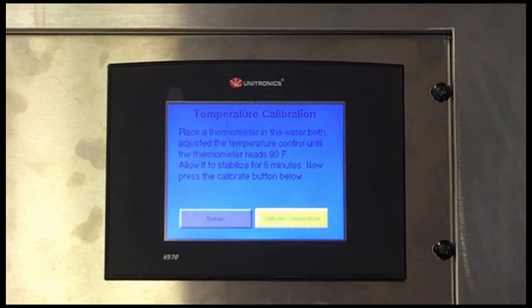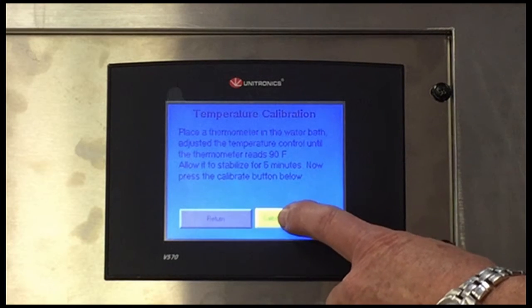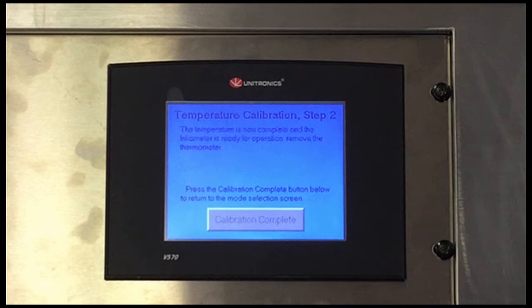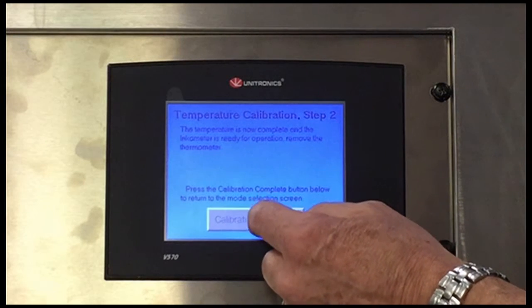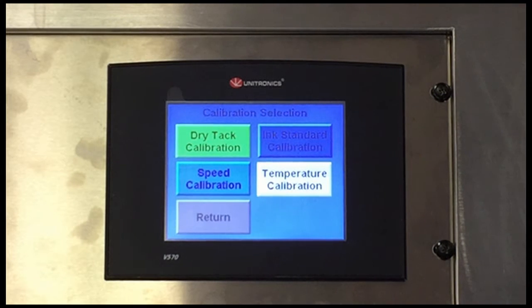What it's telling you to do is to set your temperature bath to 90 degrees Fahrenheit, because that's the standard operating temperature for this machine. So you're going to get a thermometer, hopefully something like a digital thermometer that's NIST traceable, so we know that it's accurate. And when we're sure that that water temperature is at 90 degrees, then we just simply press that, and now it's going to take whatever information is coming from our temperature probe and set it to 90 degrees. Very simple. We didn't make the calibration any more complex than that because we're really only operating around 1 point. So that is certainly suffice.